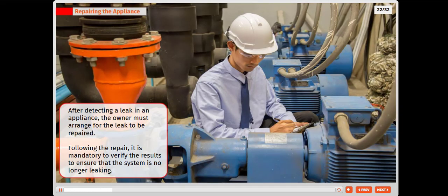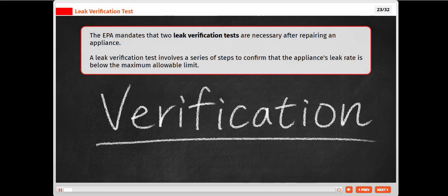After detecting a leak in an appliance, the owner must arrange for the leak to be repaired. Following the repair, it is mandatory to verify the results to ensure that the system is no longer leaking. The EPA mandates that 2 leak verification tests are necessary after repairing an appliance. A leak verification test involves a series of steps to confirm that the appliance's leak rate is below the maximum allowable limit.